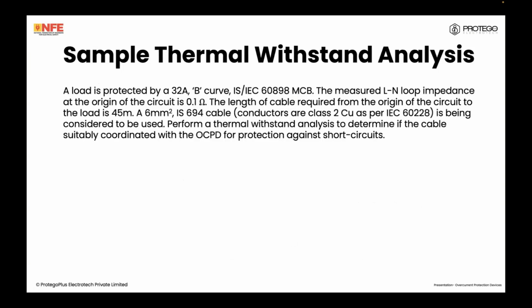Now, we'll do a sample. A load is protected by a 32 ampere IS/IEC 60898 MCB. The measured line to neutral impedance at the origin of the circuit is 0.1 ohms. The length of the cable required from the origin of the circuit, which is the point of commencement of supply, to the load is 45 meters. A 6 square mm IS 694 cable, with class 2 conductors as per IEC 60228 or IS 8130, is being considered to be used.